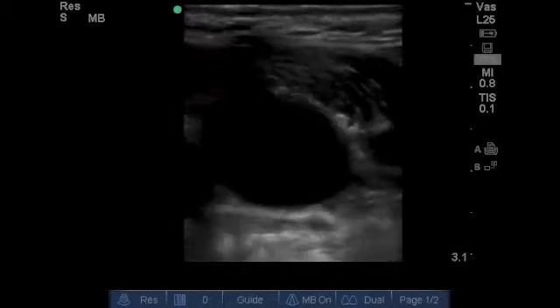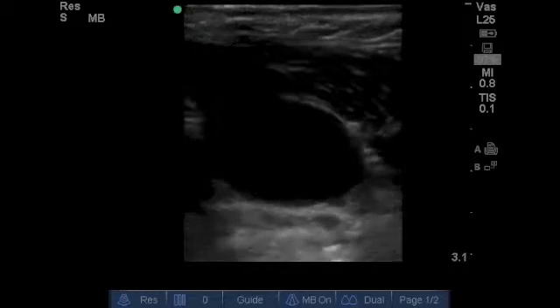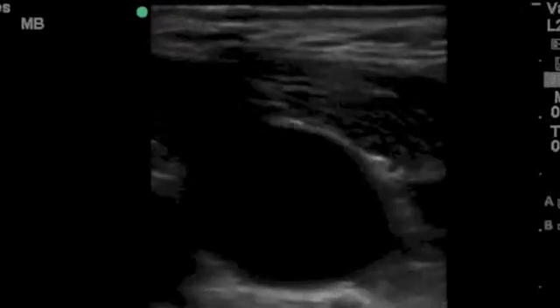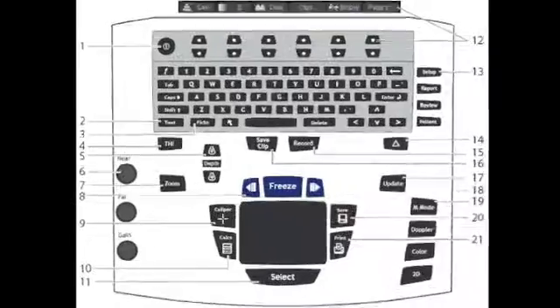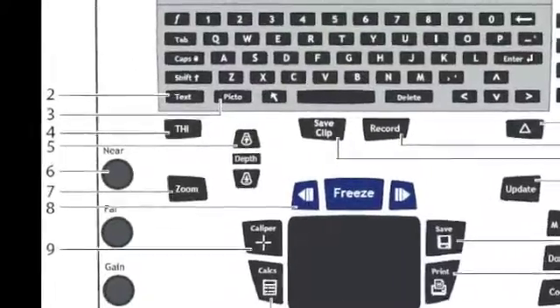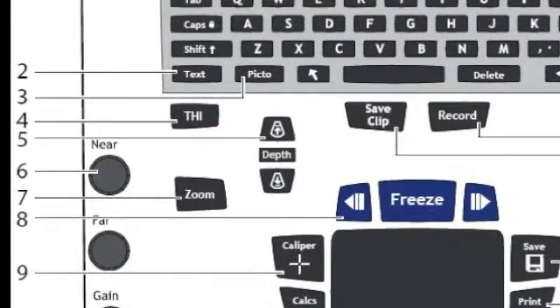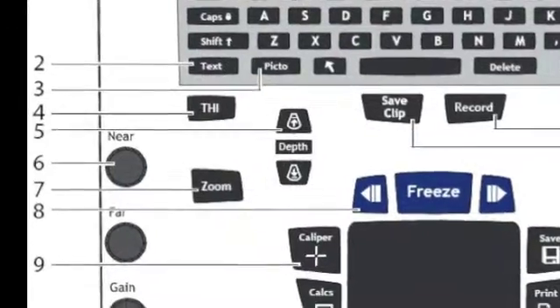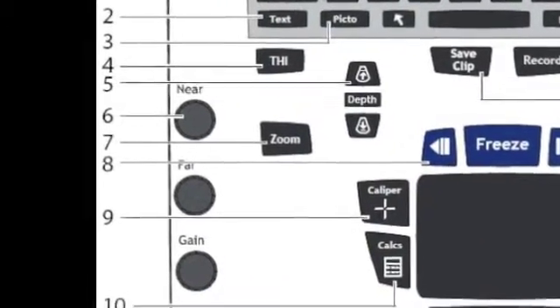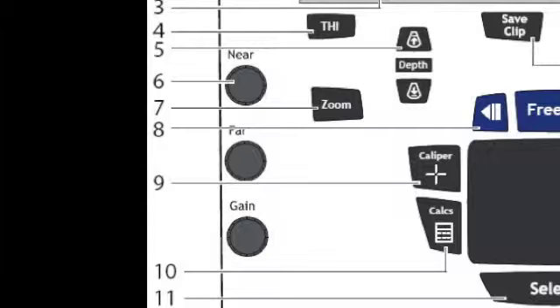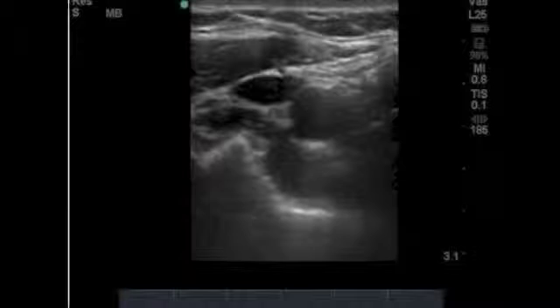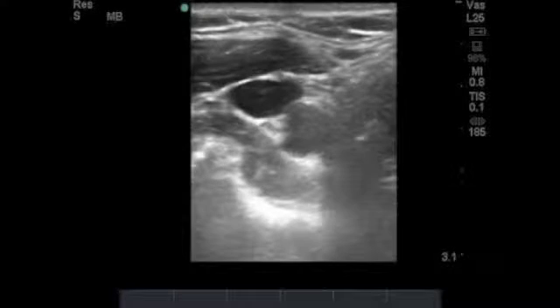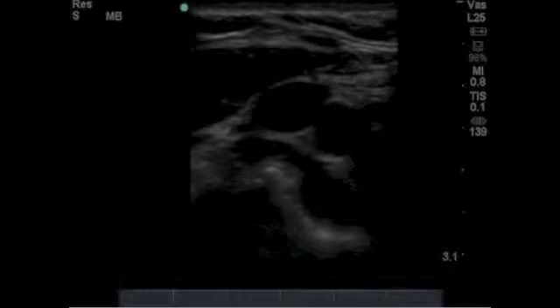The image generated by the ultrasound probe is centered on the screen. The top of the screen correlates with the tissue closest to the probe. On the right of the image are markings denoting the scale of the image. The depth or the scale of the image can be adjusted by pressing the depth buttons. To adjust the quality of the image on the screen, use the gain buttons. The gain of the overall image or just the top or the bottom of the image can be adjusted. Turning up the gain makes the image brighter, turning it down makes it dimmer.